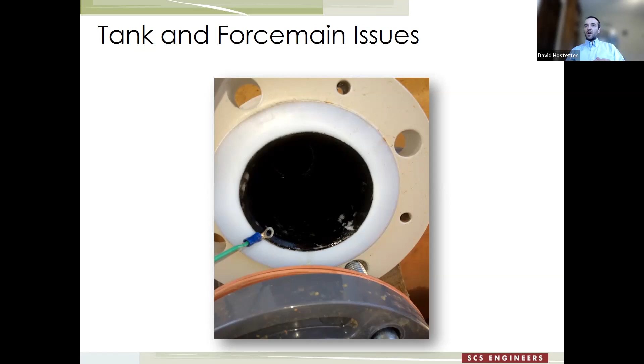So to help fix that problem, yours truly took a toilet brush to it, and Diane can show you what that looked like. Got it mostly cleaned out there, and after I got it cleaned out and reinstalled, it was back up to 100 gallons per minute. So we did two things once we figured this out. We instituted a bi-yearly cleaning on the flow meter. So again, we're trying to be proactive instead of reactive. And then we set up an alarm on the inlet flow meter so that if the recorded flow drops below 90 gallons per minute, we know about it and we're able to go out and act on it before that flow meter gets to the point where it's completely off basis.